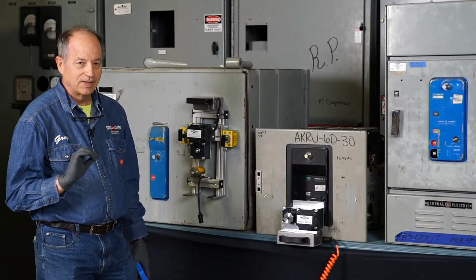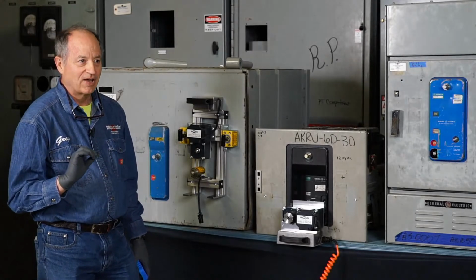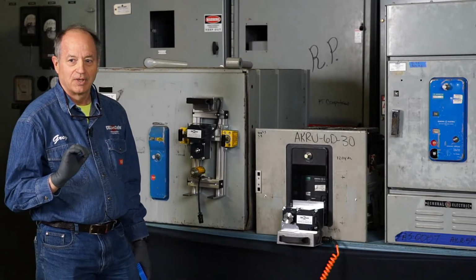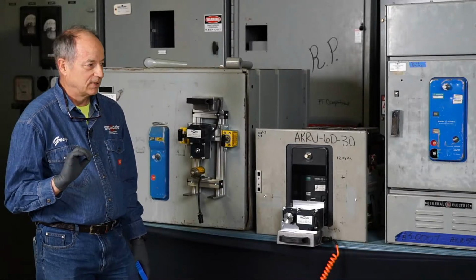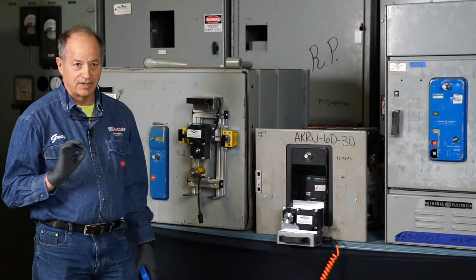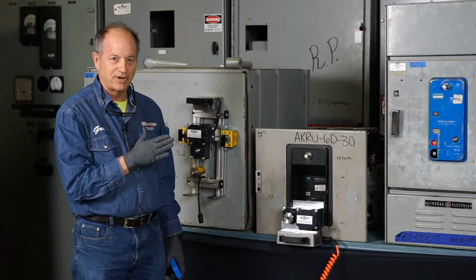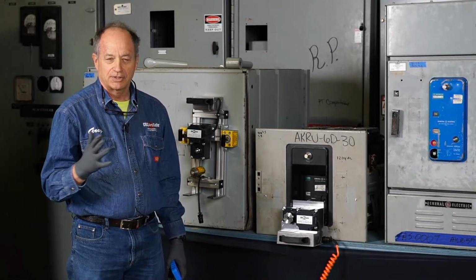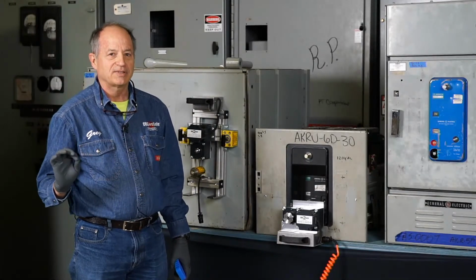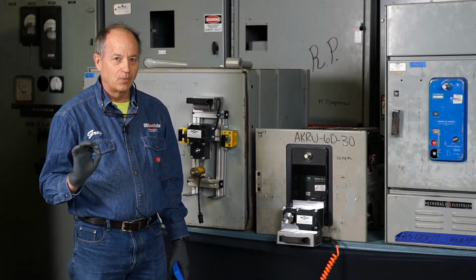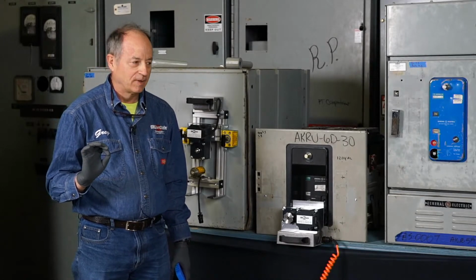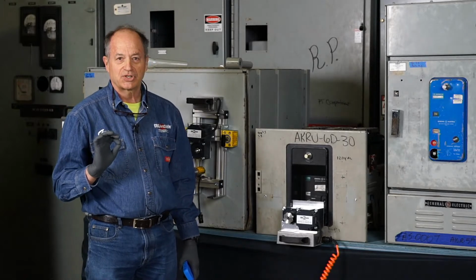It's not a contest of manhood to see how hard you can rack something onto the bus or take something off the bus. Don't let that ever get in your brain. It's got a fixed distance to travel, and it should take a certain amount of force. You want to be outside the arc flash hazard boundary while all of that happens.